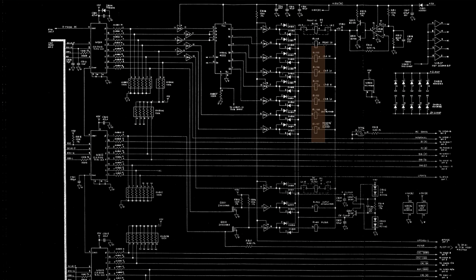The single coil latching relays used here are held at about 7 volts on one side all the time. On their other sides wait these HEF40244s, which are tri-state output, 15 volt capable push-pull drivers. So their output pins can either be high impedance to do nothing, push 15 volts in to flip, or pull to ground to deflip, or the other way around.